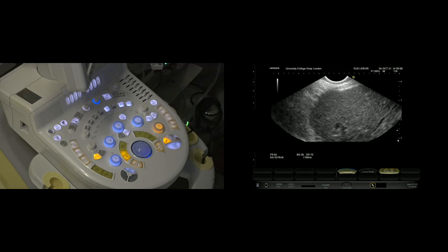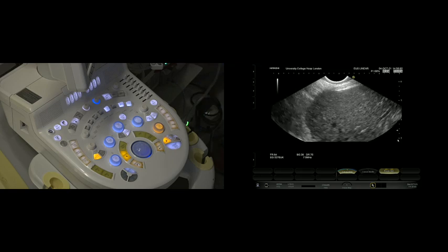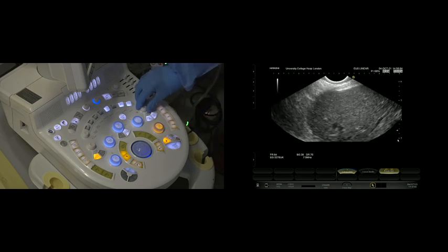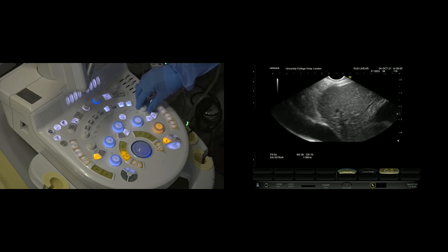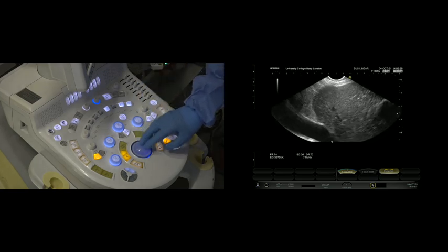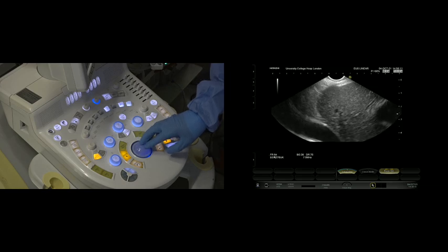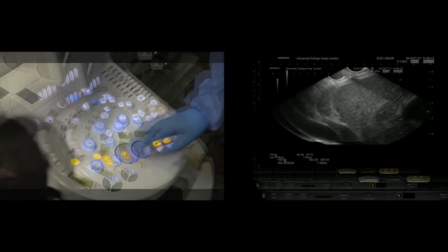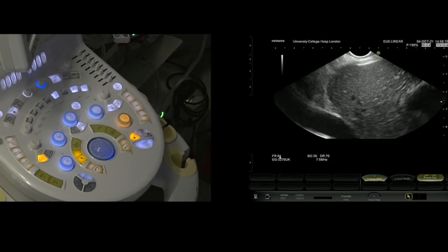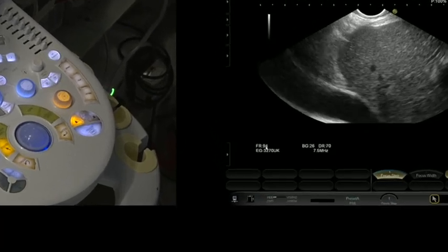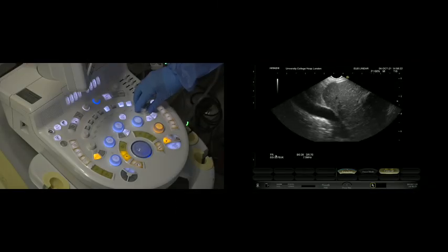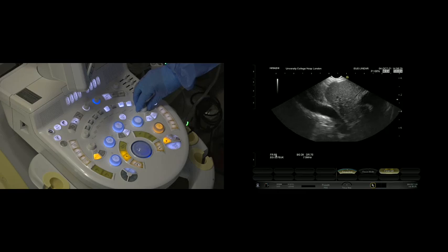We're not doing anything to the image quality, we're just reducing the depth of the view. An important feature of image quality is this number down here. FR means frame rate. The higher the frame rate, the more frames per second we're generating by the system, and therefore the better the image. By changing the gain, we're not doing anything to the frame rate or how hard the machine is working.